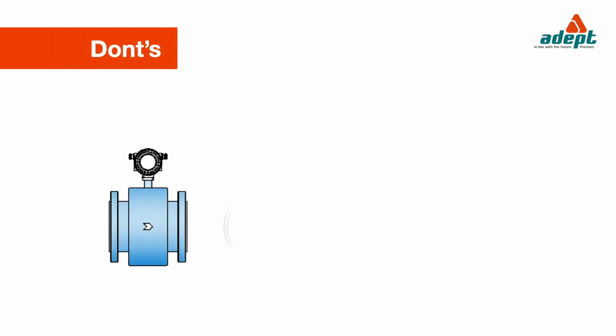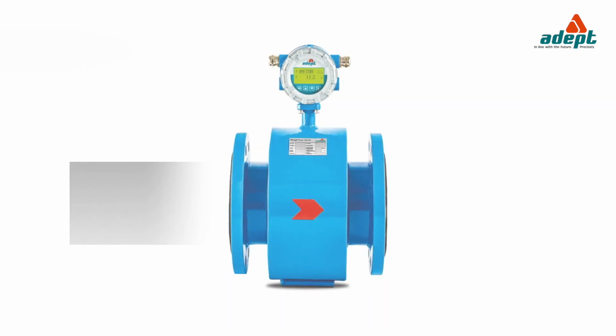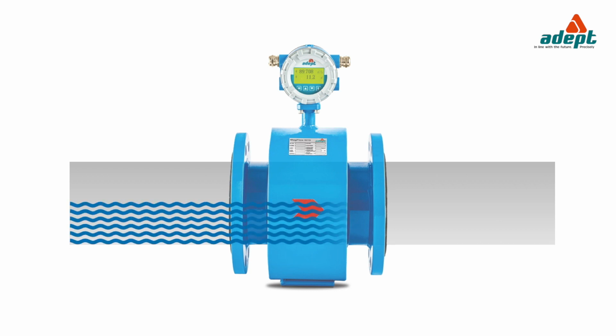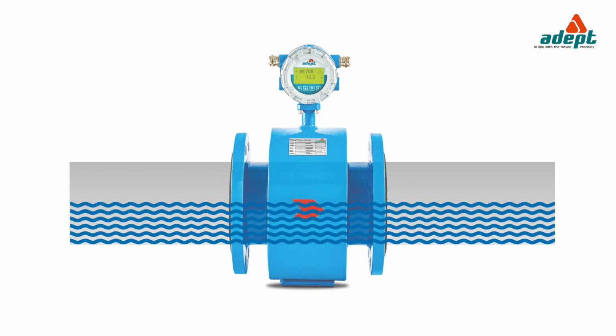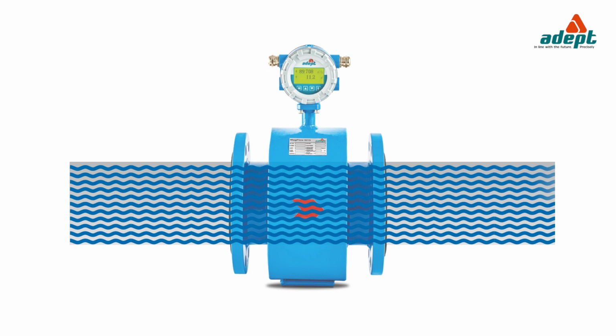Don'ts. Never install the flow tube in a way that will cause it to remain empty. Even partial flow should be avoided. Pipeline layout should be modified in such a way that the flow tube will always remain in full bore condition with water.